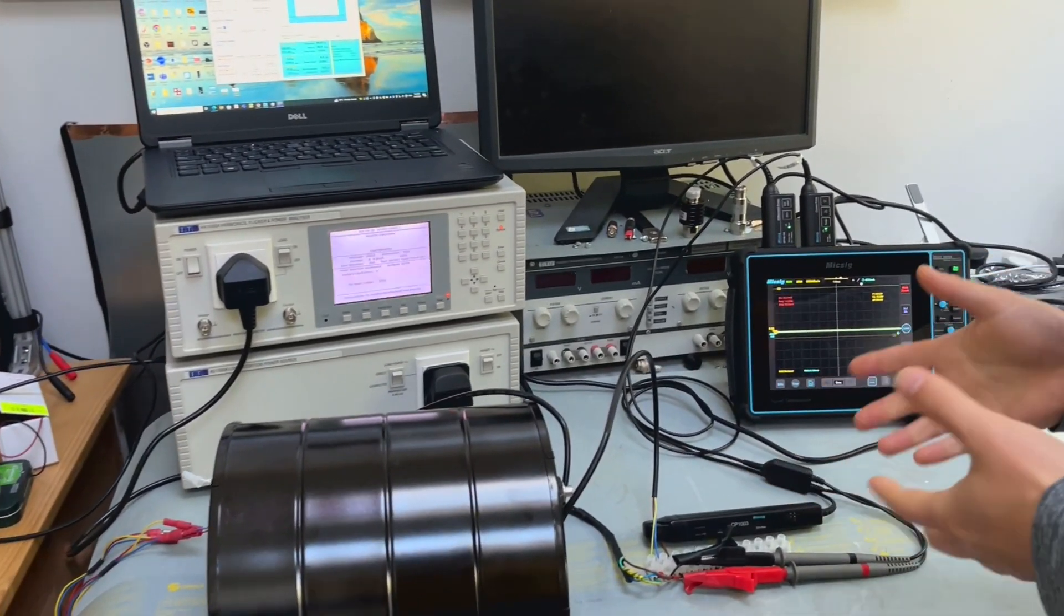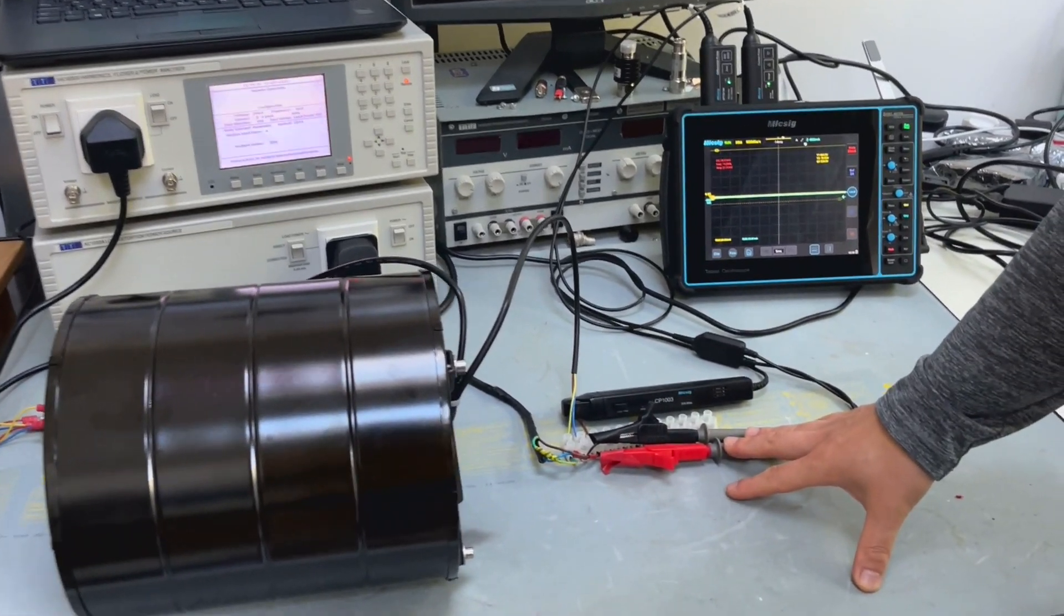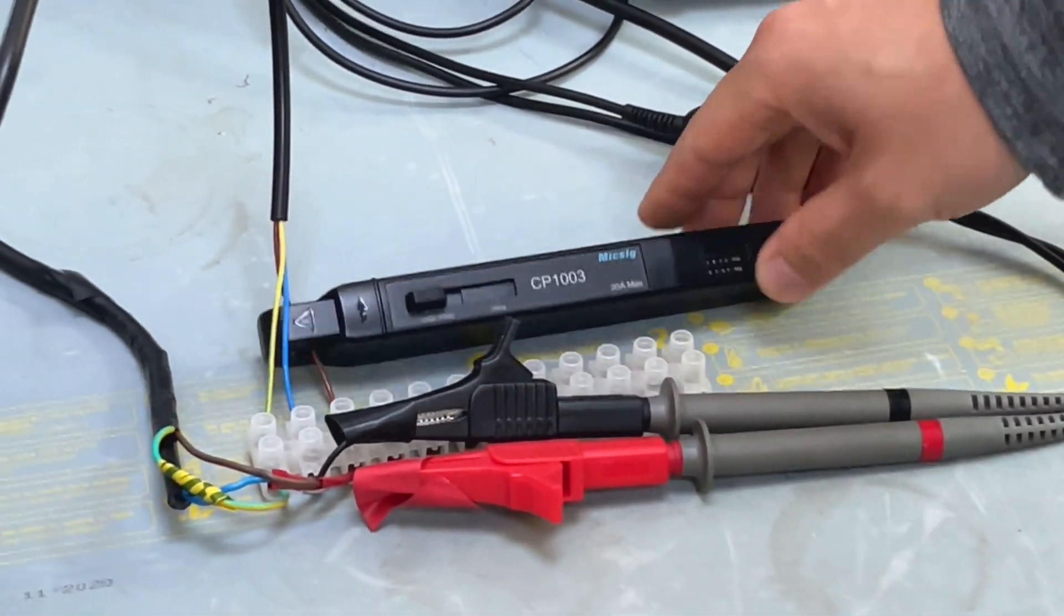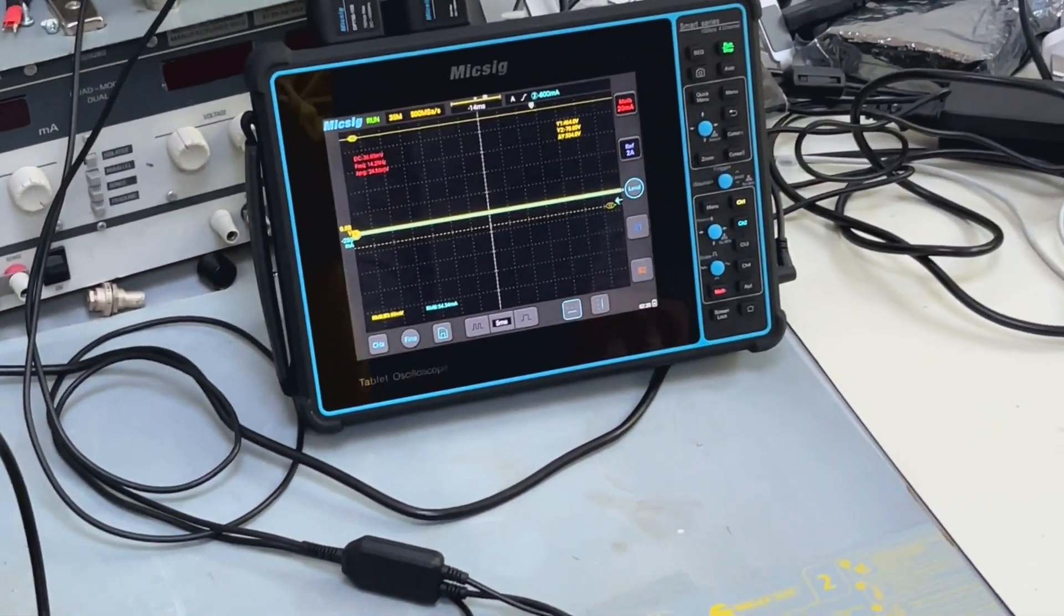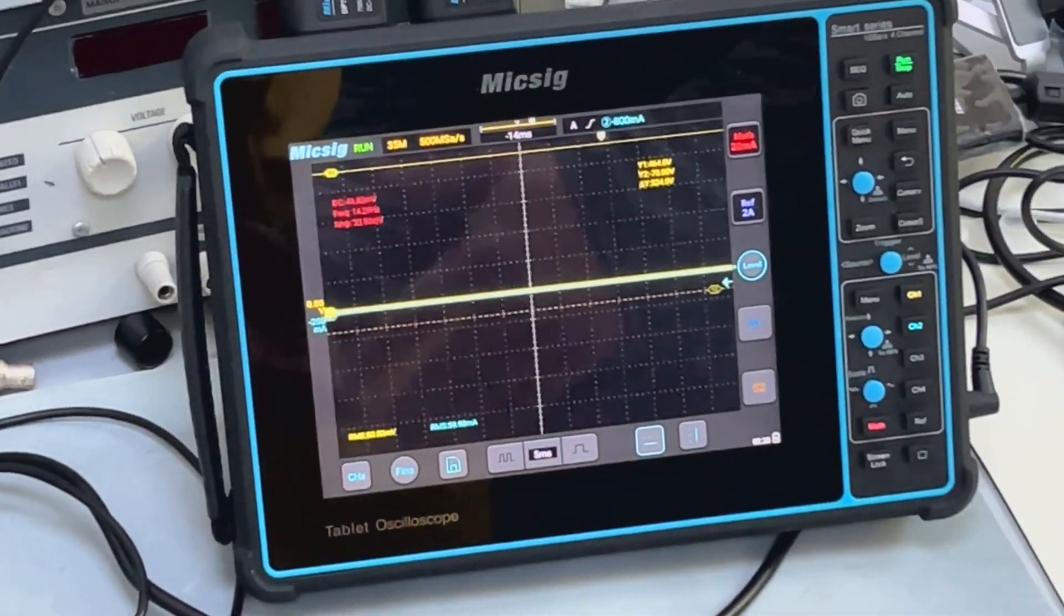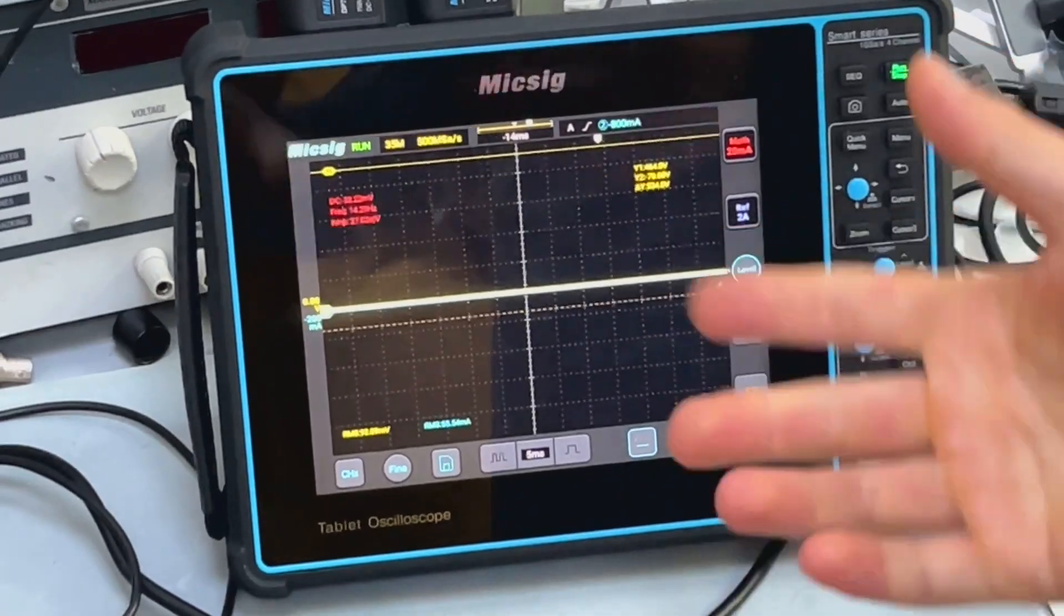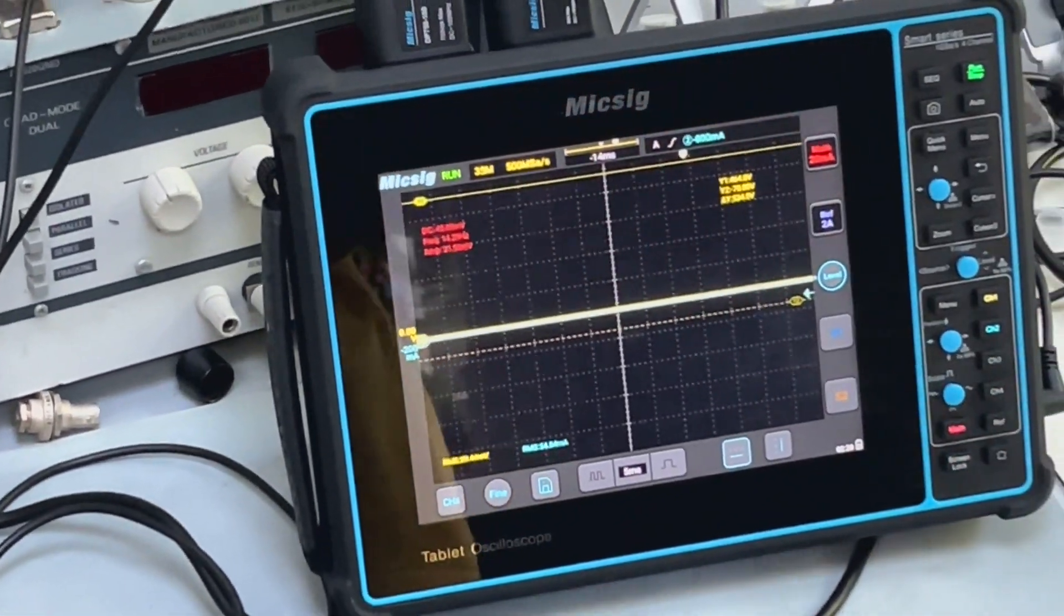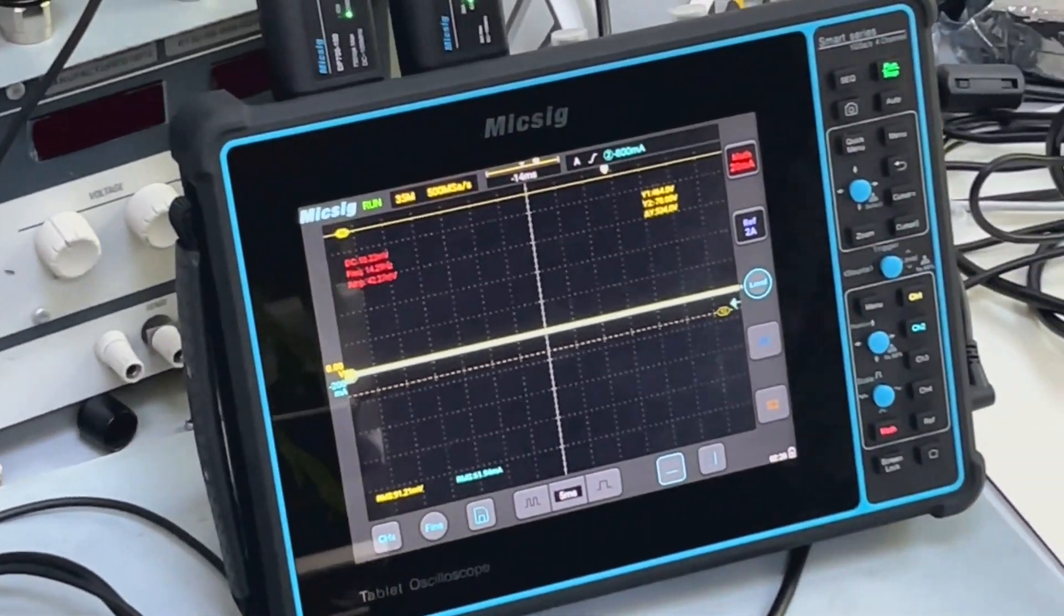In order to monitor the voltage and current waveform, here we have a high voltage differential probe and a current probe connected in this case. And we're using a mixed-signal oscilloscope to monitor both the mains voltage and current in this case. This oscilloscope also has the math function that allows you to perform an FFT analysis of the current waveform, which you will see later.